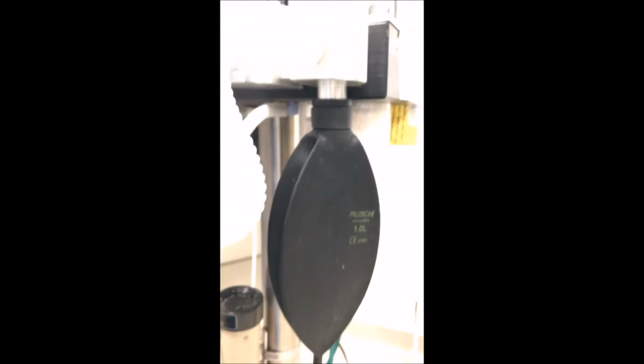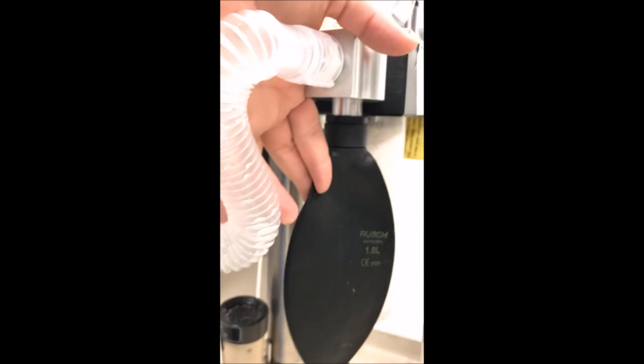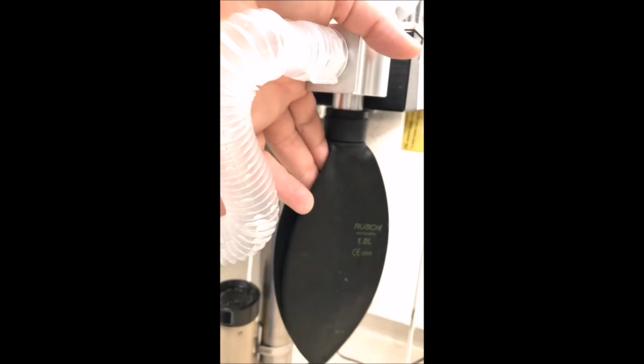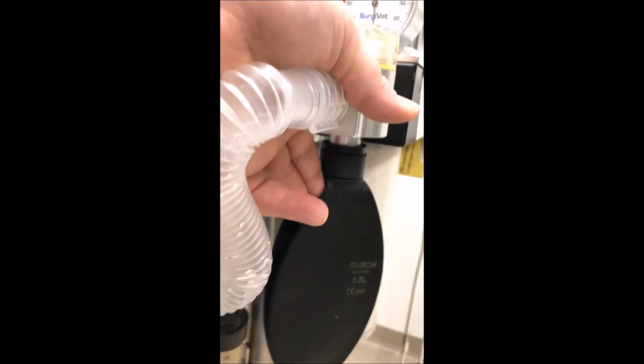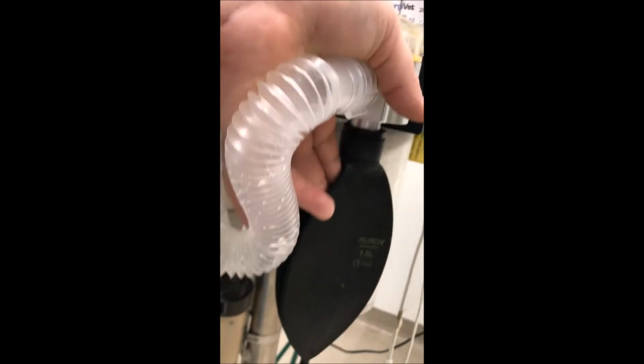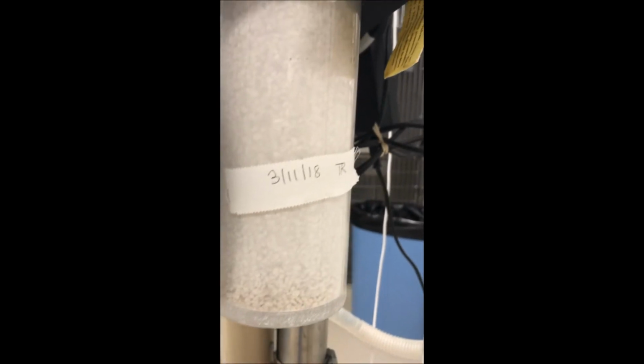Down below here is our reservoir bag. So as the patient exhales, a mixture of CO2 and isoflurane sit in here. That's why it's called a reservoir bag. Some can be inhaled back in. And then we have our soda lime canister that collects our CO2. We monitor this and change it. And then obviously we have a date here of when it was last changed.